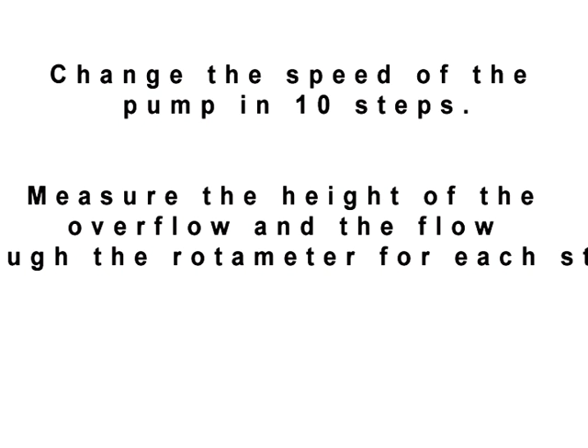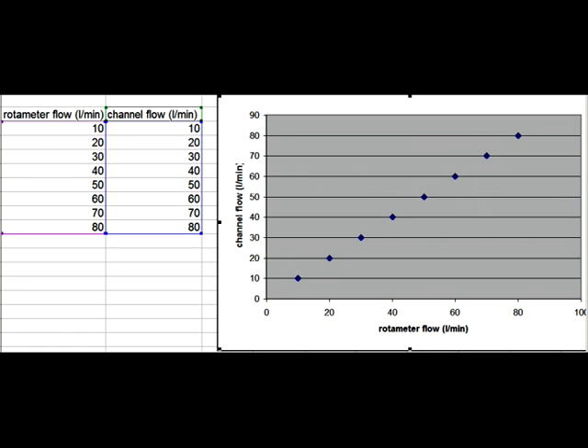If you actually want to perform the experiment, what you can do is you can change the speed of the pump in 10 steps. For each step, measure the flow through the rotameter and measure the height of the water in the overflow. If you document everything in a table and plot a graph out of it, you can see how accurate your measurement has been.